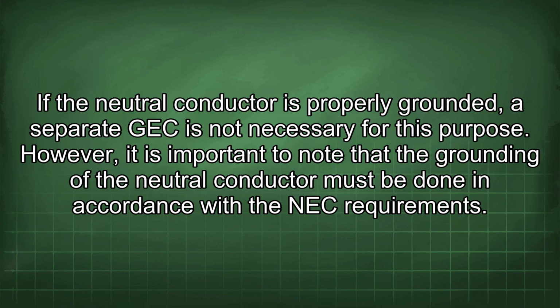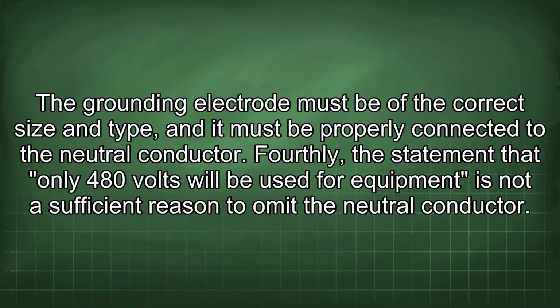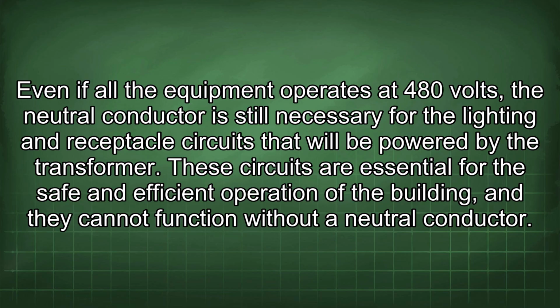However, it is important to note that the grounding of the neutral conductor must be done in accordance with the NEC requirements. The grounding electrode must be of the correct size and type, and it must be properly connected to the neutral conductor. Fourthly, a statement that only 480 volts will be used for equipment is not a sufficient reason to omit the neutral conductor. Even if all the equipment operates at 480 volts, the neutral conductor is still necessary for the lighting and receptacle circuits that will be powered by the transformer.